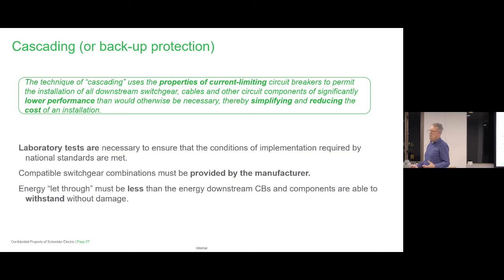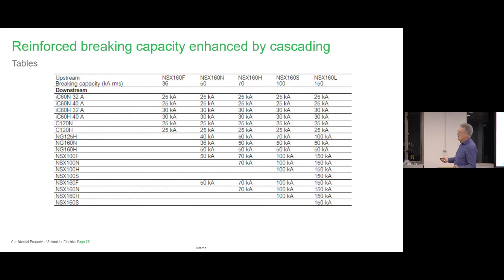They're really important information. If we want to apply cascading, we've got to be able to do all this, and that means this table. And this table is the money table. The money table means that if we select one of these, we can enhance the breaking capacity of what, it doesn't say what that is, but I know what it is. It's a 6 kA breaker, up to 25 kA, as long as we're using this fault limiting breaker upstream. As long as we're doing that, then we can achieve this level.